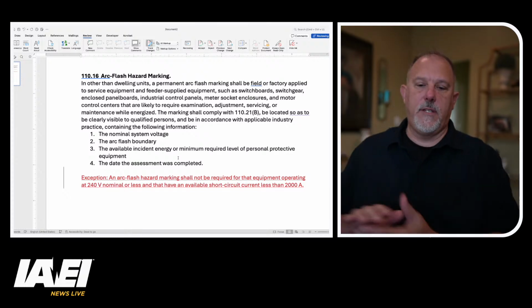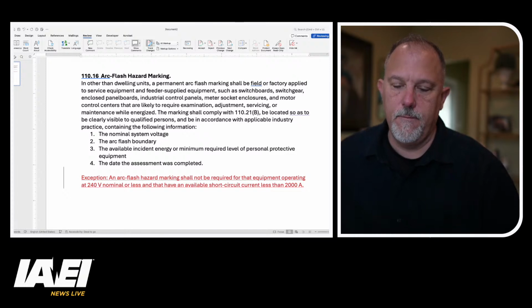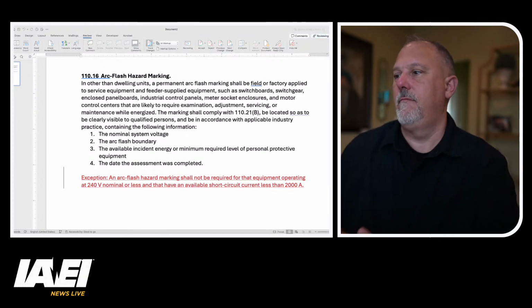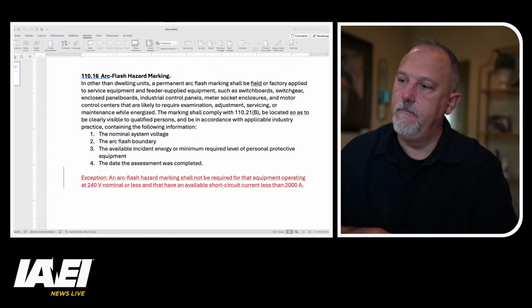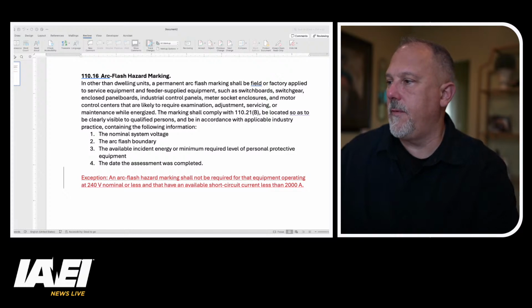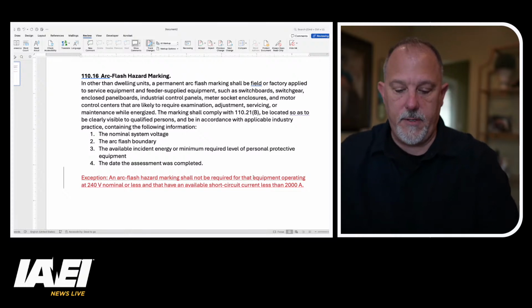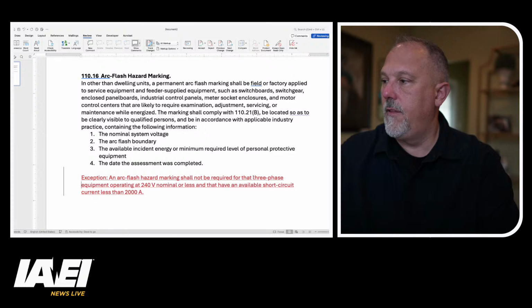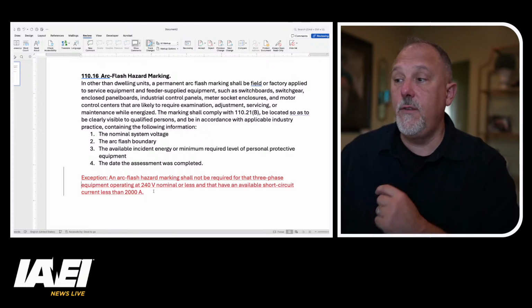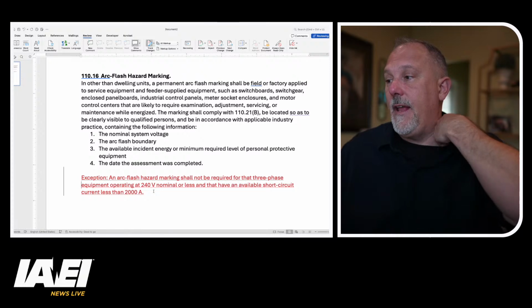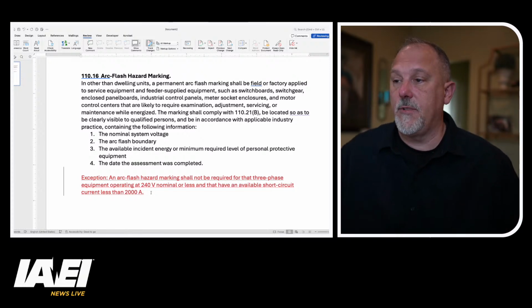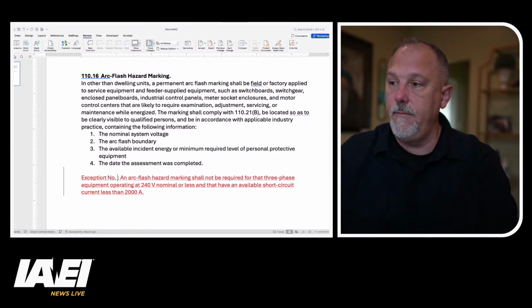That is what I would suggest to round off for next cycle. Yep, and that is shall not operating at 240 volts nominal or less that have an available short circuit current. Now this is required for three-phase equipment. Three-phase equipment operating at 240 volts nominal or less and that have an available short circuit current less than 2,000 amps. That would be exception number 1.